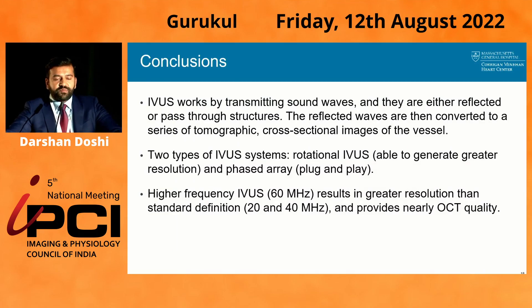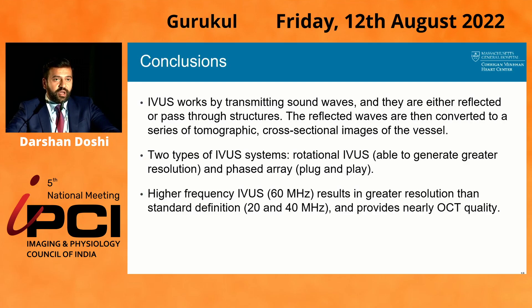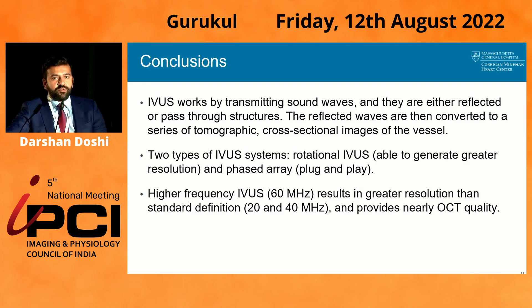In conclusion, IVUS works by transmitting sound waves that are either reflected or pass through tissue; whatever is reflected back generates the cross-sectional images. There are two types of IVUS systems — rotational and phased array — with phased array giving lower resolution compared to rotational IVUS. Now with higher-frequency 60 MHz catheters, you can get nearly OCT-quality imaging.